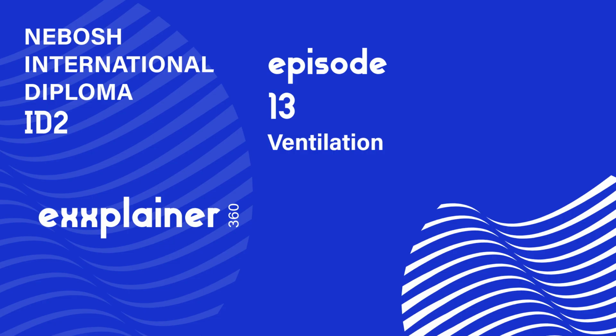Well, number one, the OEL has to be pretty high. Stuff can't be super toxic. Number two, it needs a low vapor pressure. It can't evaporate too quickly. But the real killer, the absolute deal breaker, is proximity. If the worker is right there where the contaminant is being generated, especially near their breathing zone, DV is useless. Because they're breathing it in before it even gets diluted. Exactly. The concentration might be fine 10 feet away, but right at the source, way too high. So the source needs to be relatively far from the worker.